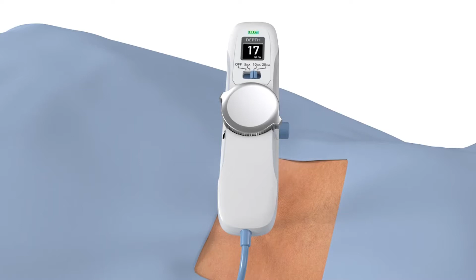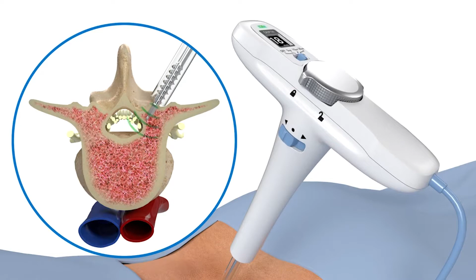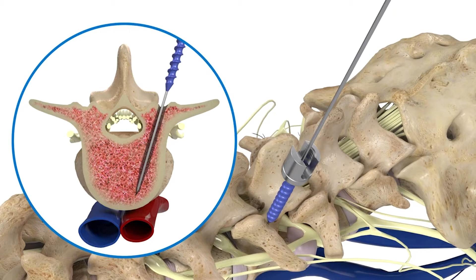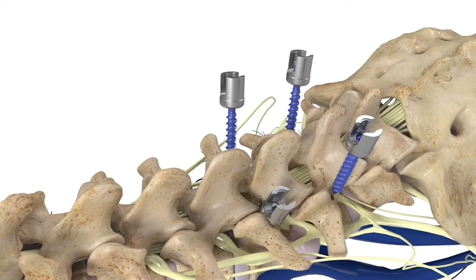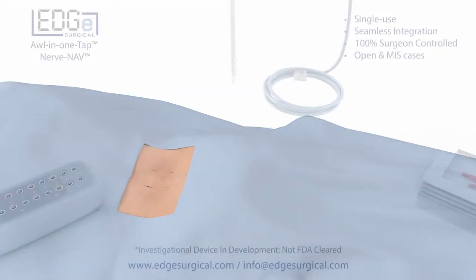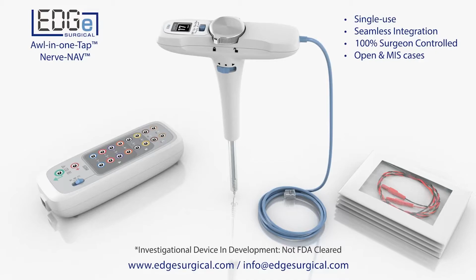A 17mm initial depth is displayed on the digital screen, and a flashing green light indicates no triggered EMG nerve detection is occurring. As the surgeon advances the device with the ratcheting handle, if the trajectory begins to veer toward a nerve, the Awl-in-one-Tap will indicate this via a flashing red signal and audible notification. The surgeon can also adjust the amount of milliamps to further provide feedback of nerve proximity. Once the surgeon has configured their desired screw pathway via the digital depth measurement and triggered EMG, the surgeon can remove the inner stylet and replace it with a guide wire. Then, the ratcheting handle can be switched to reverse and the Awl-in-one-Tap can be removed. A screw is then inserted and the process is repeated until all pedicle screws are properly placed. The Awl-in-one-Tap combines several features, providing a safer tool when placing spinal pedicle screws and minimizes the number of surgical steps required.